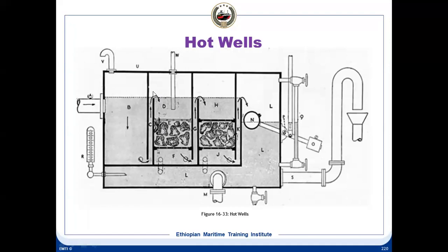There normally is an observation port, or there could be an oil in water probe also. We had talked about this in the last class. So the possibility of the oil reaching this feed pump suction is pretty remote. Like I said, the hot well has to be pretty empty, unless the hot well is full of oil, in which case we are already in a pretty bad situation.